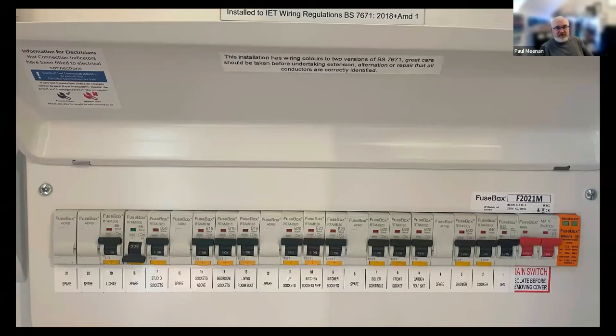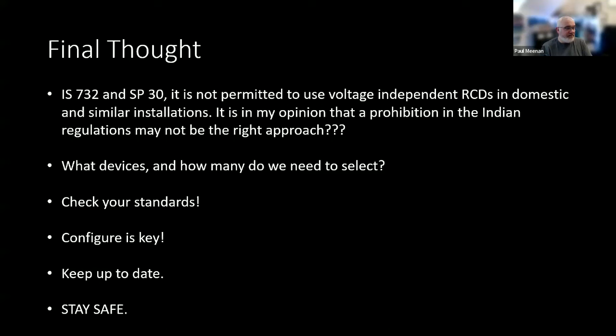But that gives you a very robust benchmark for safety. So that's my one downstairs. Kind of final thought, really, while I've been on this journey, and thank you very much for coming on it with me. Indian Standard 732 and SP30, it is not permitted to use voltage independent RCDs in domestic and similar installations. However, in my opinion, and I'm sure Chris will agree, the prohibition in the Indian regulations may not be the right approach. Maybe there's a little bit more work needs to be done there.